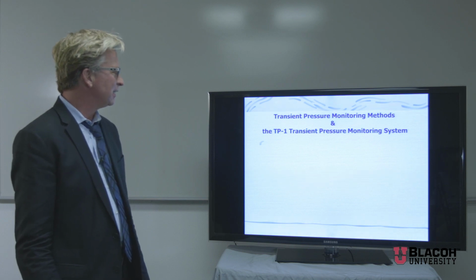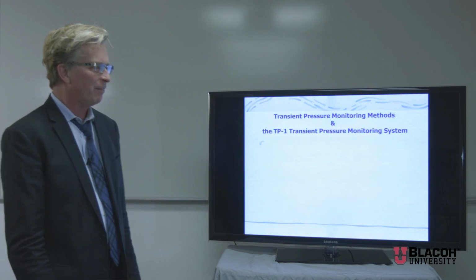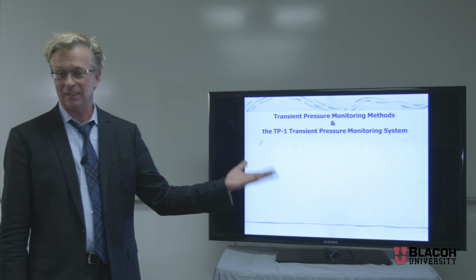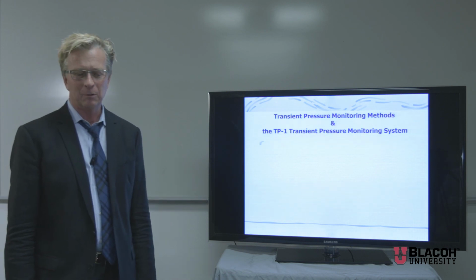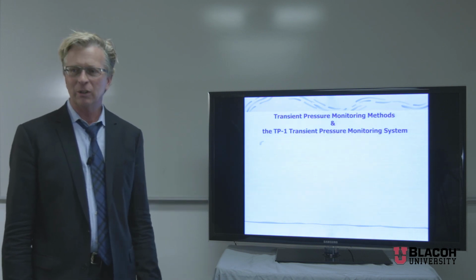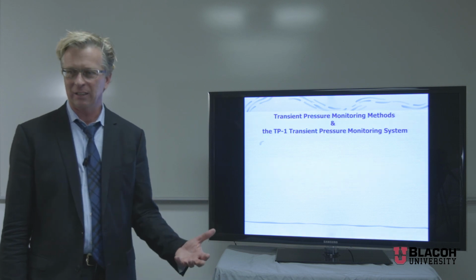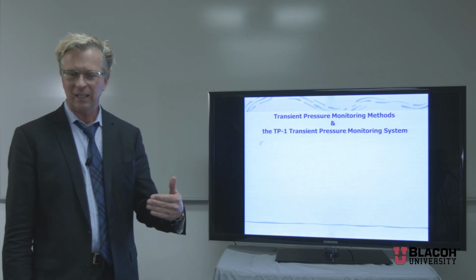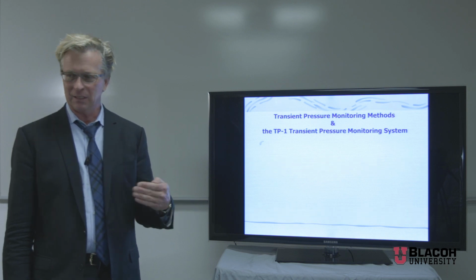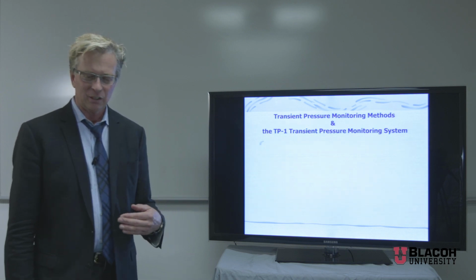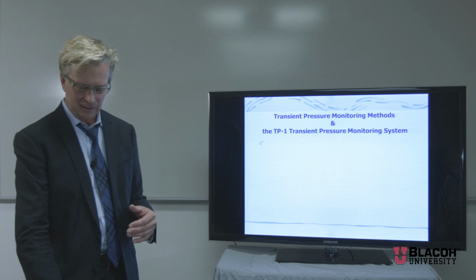So whose fault is it? So we look at recording the data in the event. In this case, the contractor is thrown under the bus. He'll come to us and say, okay, record the transient data that's occurring so we can say our piping system was installed properly. So you're looking at the piping system back here, and most piping systems, you'll see the pressure rating on the pipe. It's good to 285 psi. But have you ever seen the negative pressure rating of the pipe?